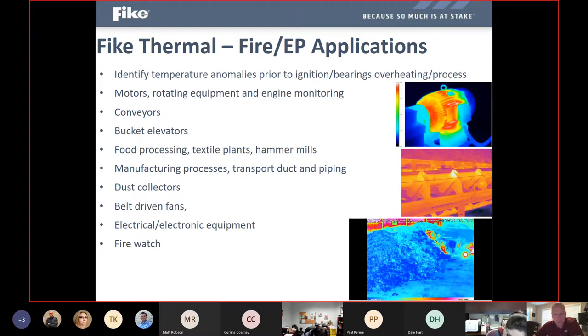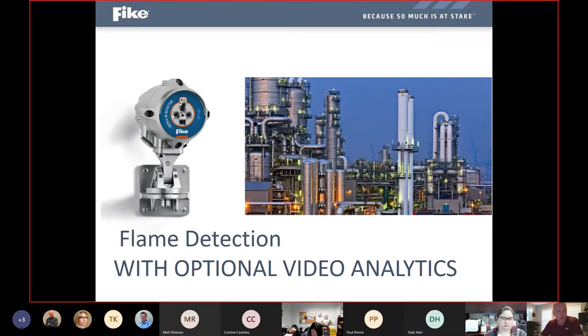a belt conveyor system. Or in the lower right there, you can see at some trash facilities where they scoop out bulk product, there is a hot spot where that loader has lifted out and taken out a pile of product that's invisible to the naked eye and is probably not hot enough to set off a heat detector. There's certainly no flame or smoke present there yet, but that is a smoldering pile underneath that pile of product that we can now identify and maybe send somebody out with a handheld CO2 extinguisher or something to try to reduce that temperature and put out that potential smoldering condition there. So a lot of different applications where we can use that thermal monitoring for detection and annunciation.